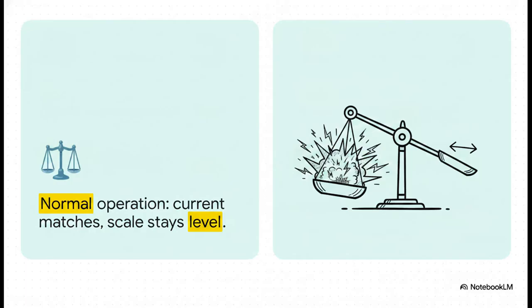Think back to that balance scale analogy. During normal operation, the scale is perfectly level. What goes in completely comes out. But if an internal fault occurs, boom, that scale tips dramatically. If the current entering the zone doesn't perfectly match the current exiting, it means only one thing. Something inside that highly protected zone is stealing current. A short circuit has created an unintended path, and that current is being diverted, usually with incredibly destructive force.